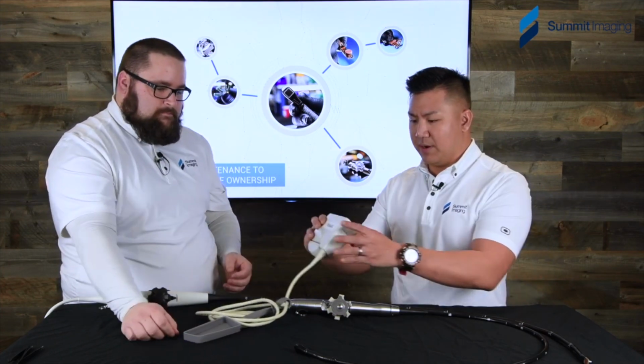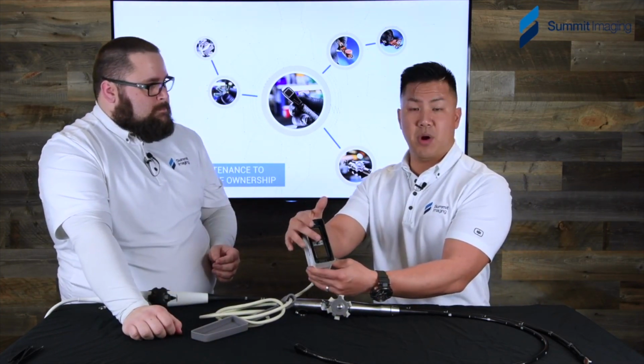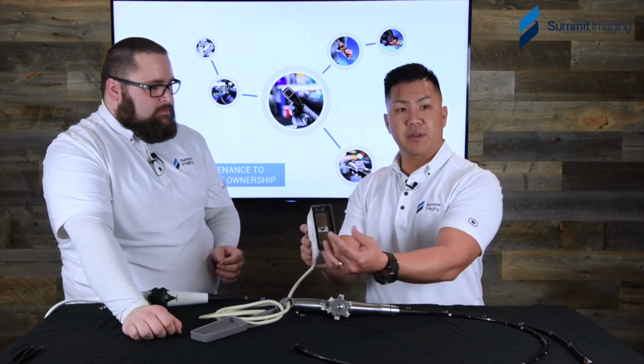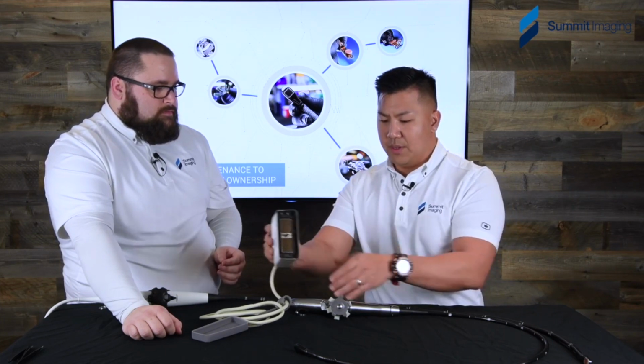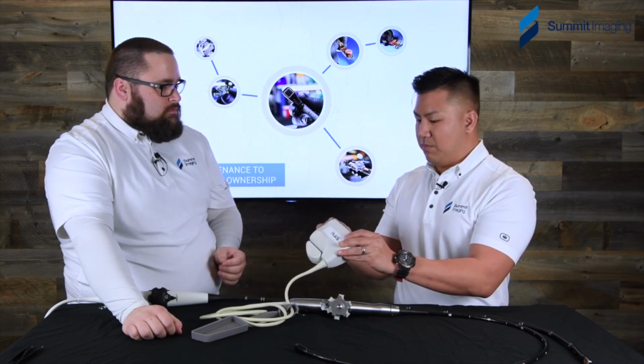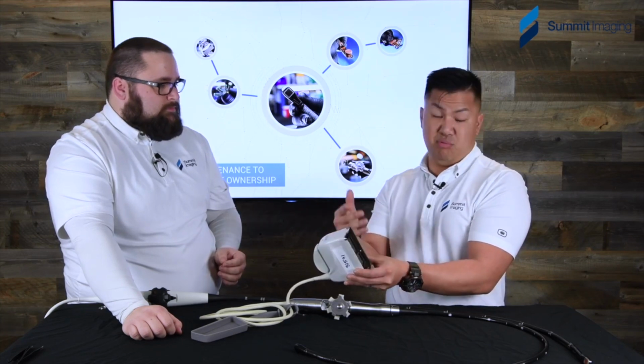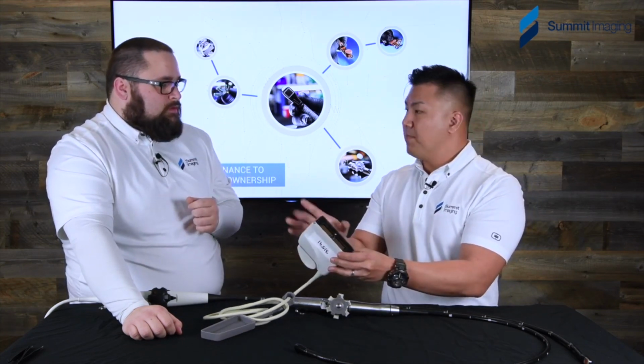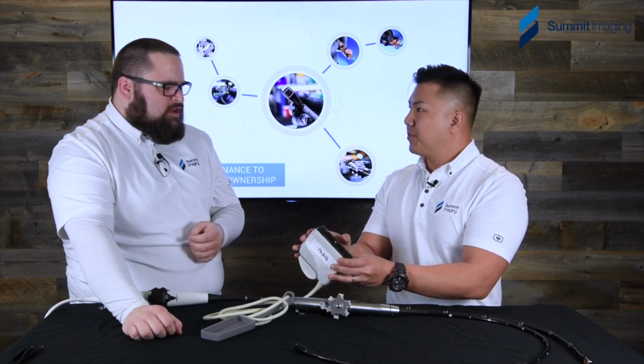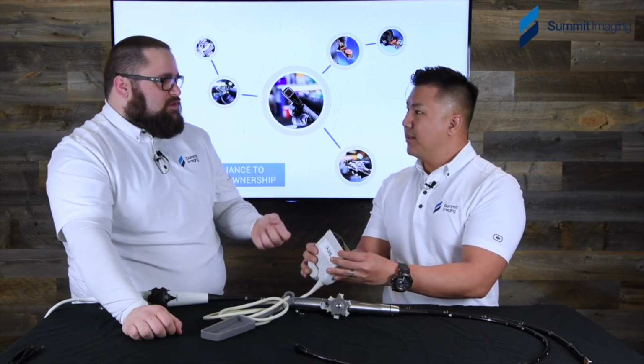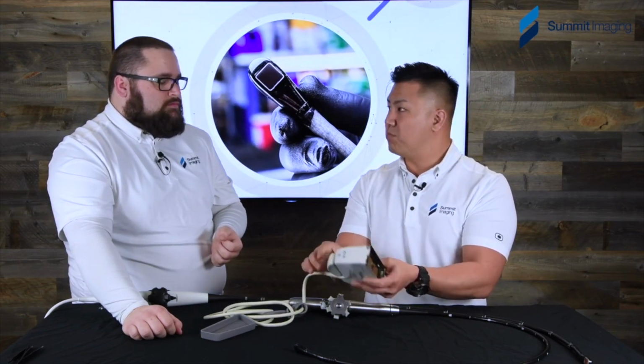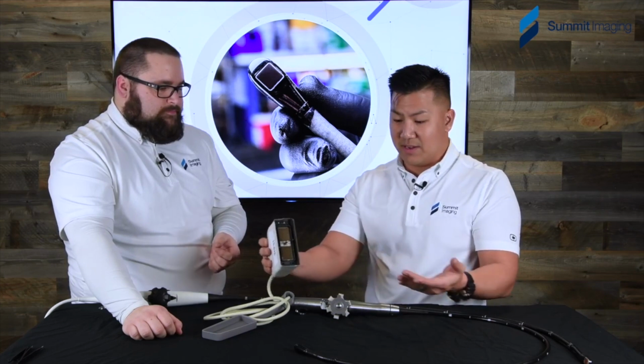So to be very clear, there are grounding pins. The locking pin is part of the ground circuit. The screws that hold the connector into the can itself are part of the grounding circuit. And we've actually seen these connectors counterfeit or improperly remanufactured, whatever term you want to use, made out of plastic. Yeah, plastic, 3D printed, and then spray painted to look metallic. But if this physical can that we knock on is not metal anymore, then it's no longer conductive. And if it's not conductive, your patient now becomes a floating ground.